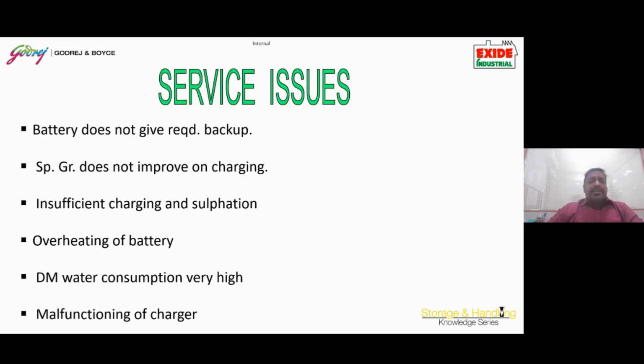Now, if specific gravity does not improve on charging, it does not mean we have to put water. There is a possibility that during transit or transportation, the battery has toppled and electrolyte has been lost, and nobody has topped up the electrolyte, or instead of topping up with acid, it has been topped up with water. So if electrolyte is lost, it has to be compensated with electrolyte.